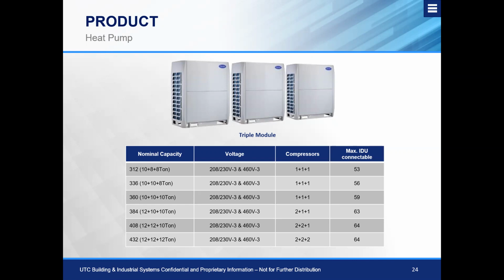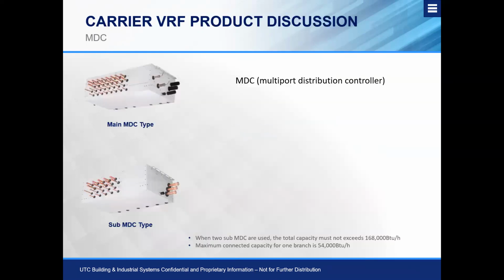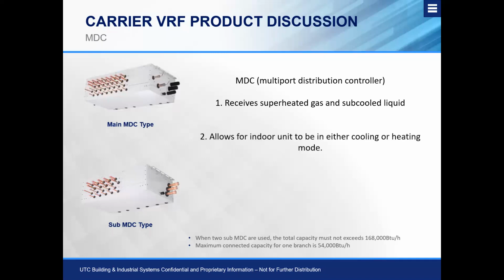And just like we talked about on the heat recovery side of things, the derate on these units will depend on what configuration of outdoor unit you're working with and also the connected capacity to that unit itself. So looking at our MDCs, we know that they are comprised of 3 main things. We know that they receive superheated gas and subcooled liquid. They allow for that specific indoor unit to be in either a cooling or a heating mode. And they distribute the amount of refrigerant to the indoor units based on that individual heating and cooling demand. And that command is sent via a communication wire from that indoor unit to its MDC or selector box.